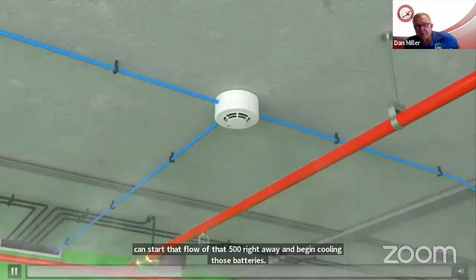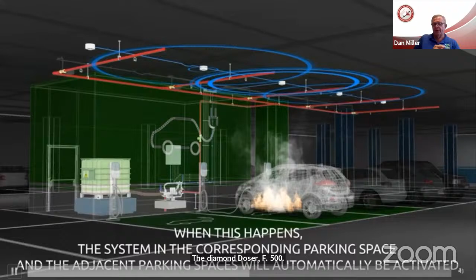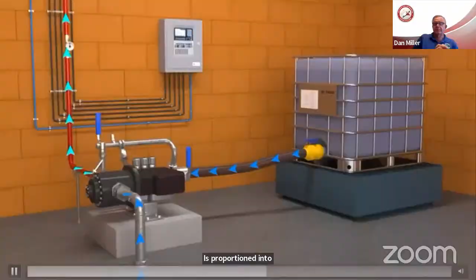Once it does turn into a fire - and occasionally they pretty much instantly turn into a fire - the system detects it, the deluge is applied through the Diamond Doser, and F500 is proportioned into the riser and fed to the deluge heads. All of this can happen in mere seconds when it comes to lithium-ion batteries.